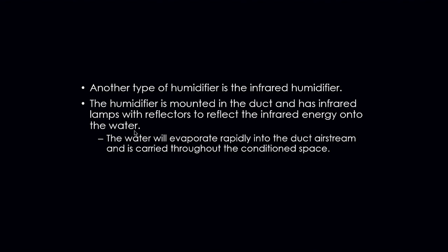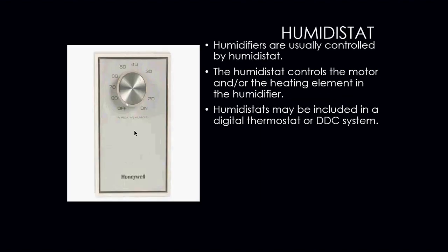Okay, another type of humidifier is your infrared humidifier. These humidifiers are mounted into ductwork and use infrared lamps with reflectors to reflect the infrared energy onto the water. Then that water will evaporate rapidly in the duct's airstream and is carried throughout the conditioned space.